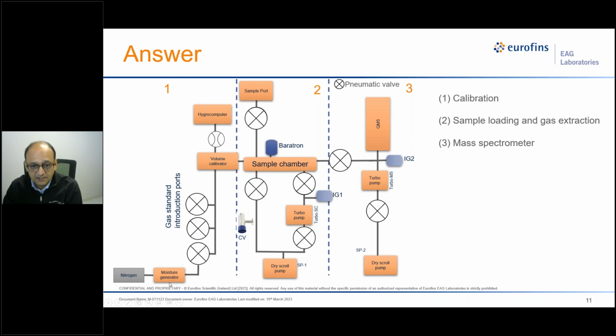Now the moisture generator has inside it a permeation tube, a NIST calibrated permeation tube, which is emitting the moisture at a constant rate. By changing the flow rate of nitrogen, we can change the concentration of moisture in the final gas that is coming out of this generator. This moisture generator is calibrated annually or as and when required, and it can provide a very highly stable gas mix that we can use for our calibration. Once it goes to the valve system, we can control the flow there, and then it goes to something called the volume calibrator. What is the function of this section?